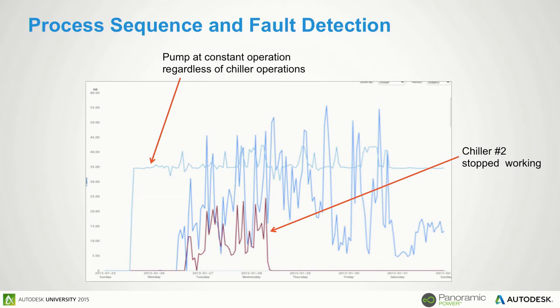What Panoramic Power allows us to do is, just by looking at the power demand over time, see whether or not a device is operating appropriately. Here's an example where a pump is consuming the same amount of energy and running at the same state, regardless of what the chiller is doing. You'd want it to replicate what the chiller is doing and turn off when appropriate.